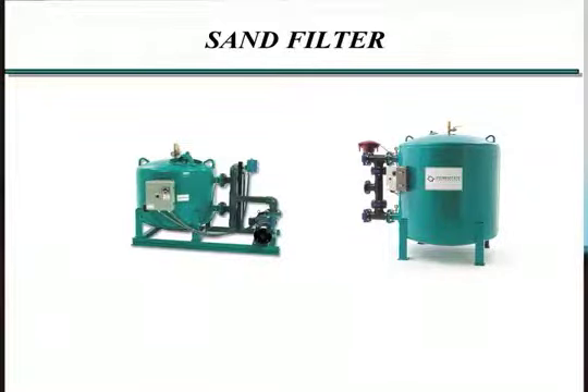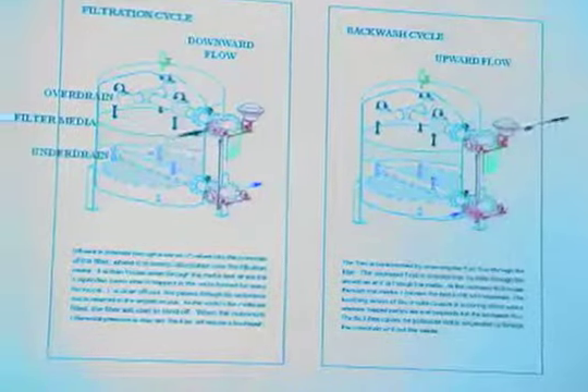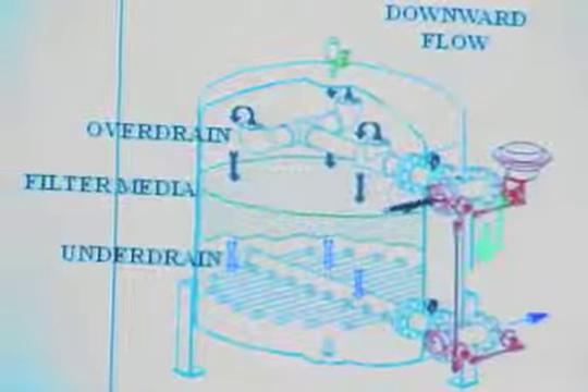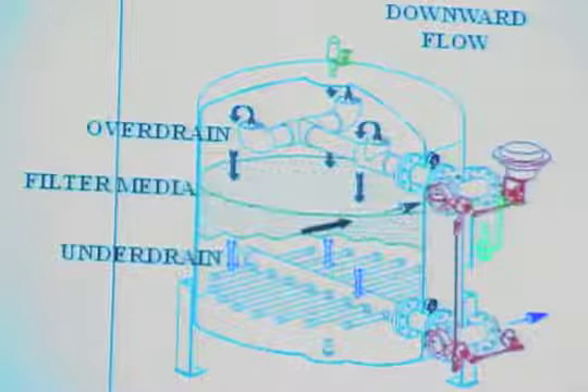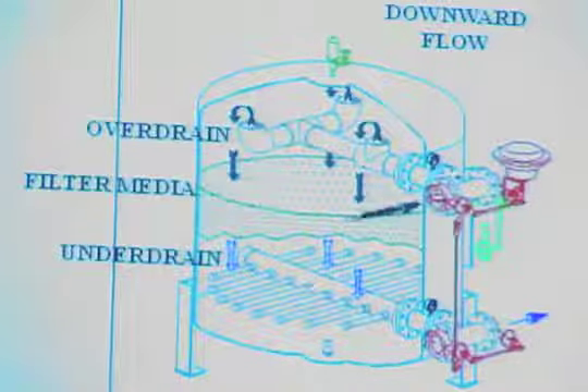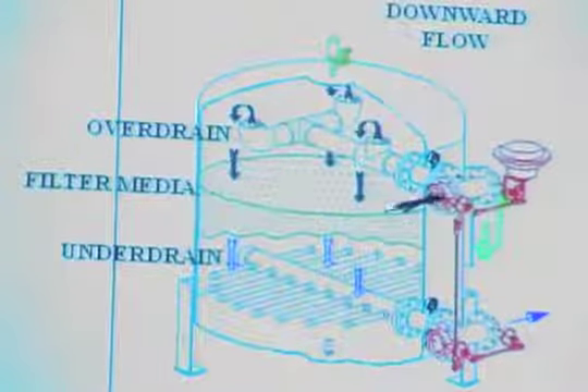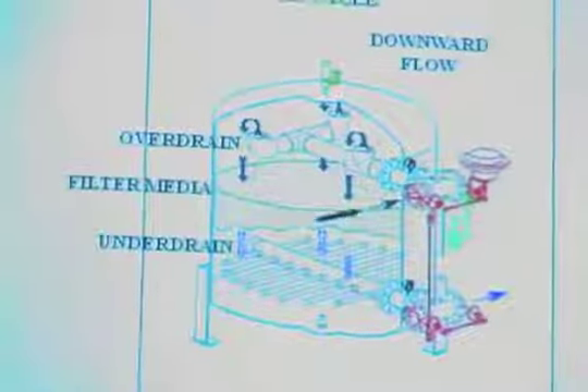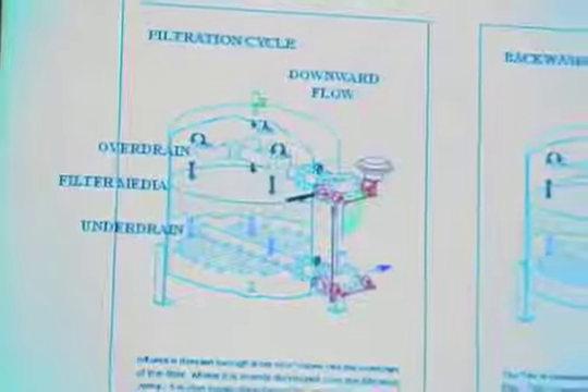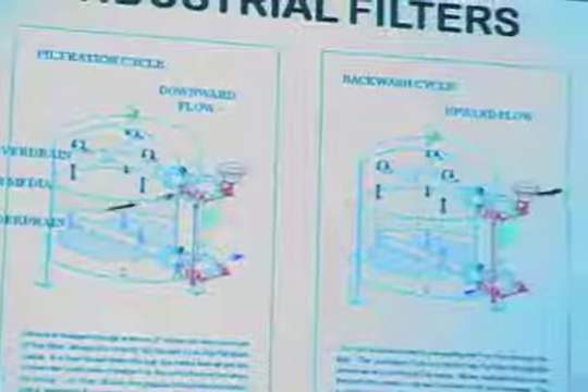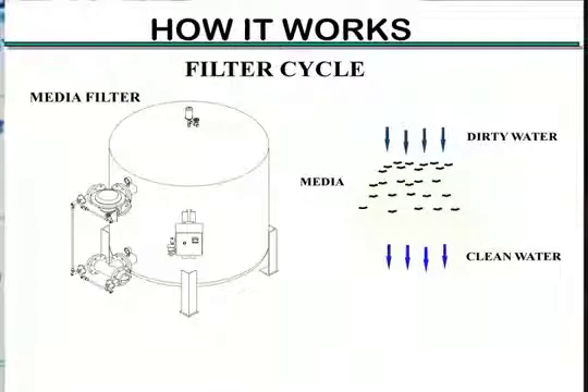Sand filters are the other common type of system used in open systems, and one of the main advantages of this type of system is it's regenerable, and you have a permanent media in there. A good diagram of this is you've got water that comes in through a distribution chamber and goes down through this permanent media. The media is selected for a certain pore size, so there are different types of medias that can be in there, and then the water leaves out through the bottom. And that goes through a series of tubes to collect the water and go back to the system. When you wash it, you kind of reverse the cycle. I've got a couple diagrams of that that show it a little better.